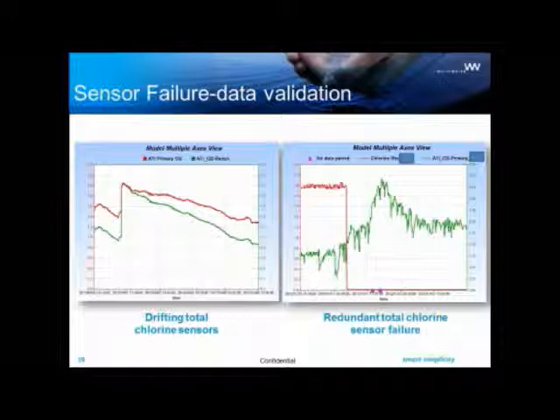In addition to that, these days we can integrate information coming from manual sampling in your laboratory using your LIMS, the laboratory information management software. So you can see the correlation between your manual sampling and your online monitoring, and then you can distinguish very clearly if a sensor starts to drift and you need to calibrate it, or if you have a problem in the water.